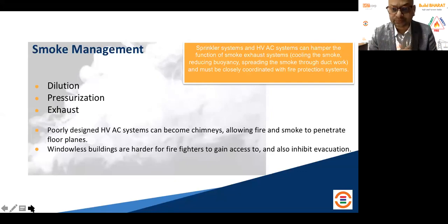That's number one. Number two, a very important topic that mostly people do not pay attention to: how the system is going to talk to my HVAC and my sprinkler system. Why does it have to be closely associated? Because when you have a sprinkler system in place expected to operate at a certain temperature, say 68 degrees centigrade...